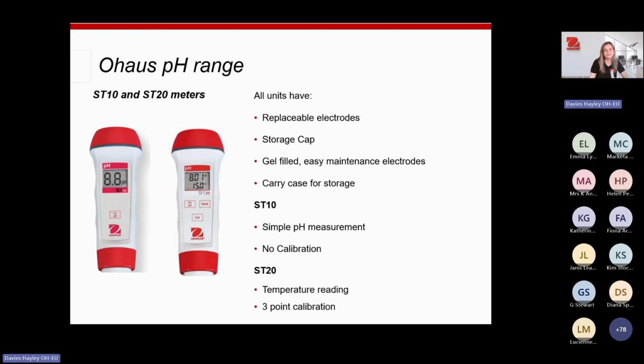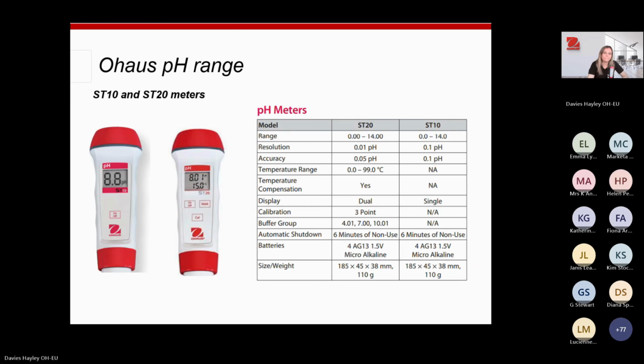For pH, we have two. We have one which is an ST10, which is just for simple pH measurement. You can't calibrate them, so you literally just pop it in, look at the number change, give it a clean, and away you go. The ST20 has an integrated temperature sensor, so you've got the temperature reading on there, and you can also do 3-point calibration as well. And you've got here just a little bit on the accuracy. It's got automatic shutdown as well. So after 6 minutes of non-use, it will switch off. You've got different buffer groups as well for the ST20.